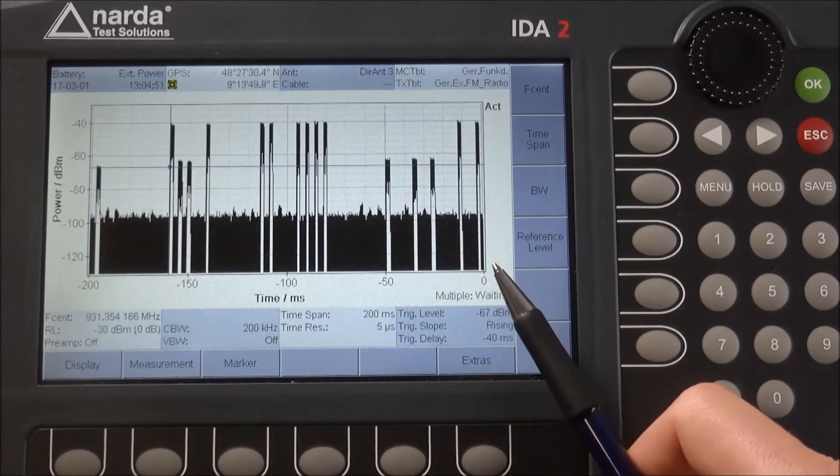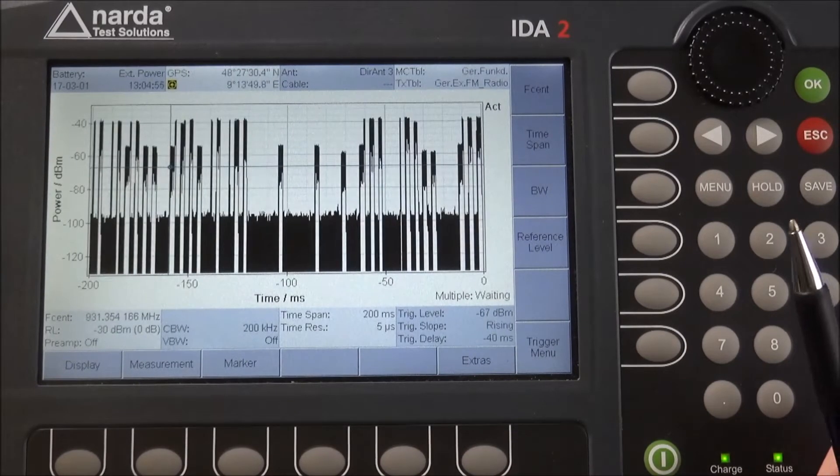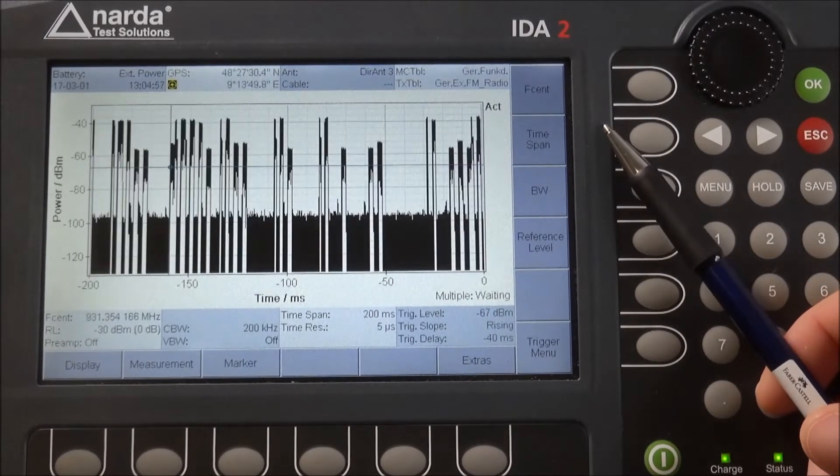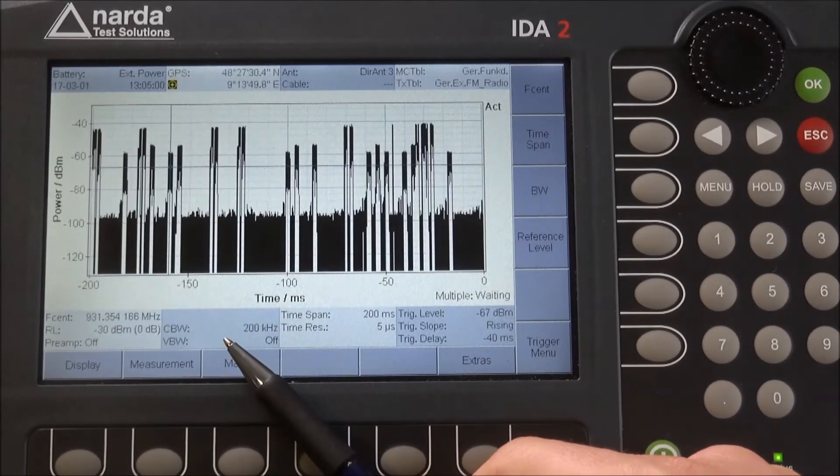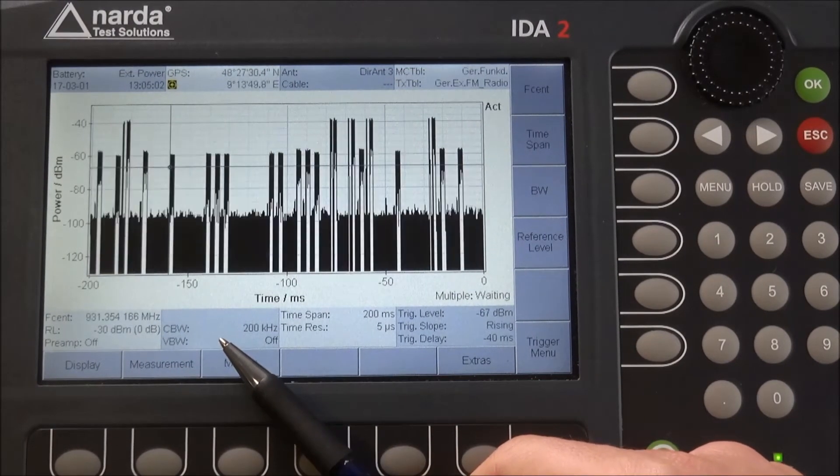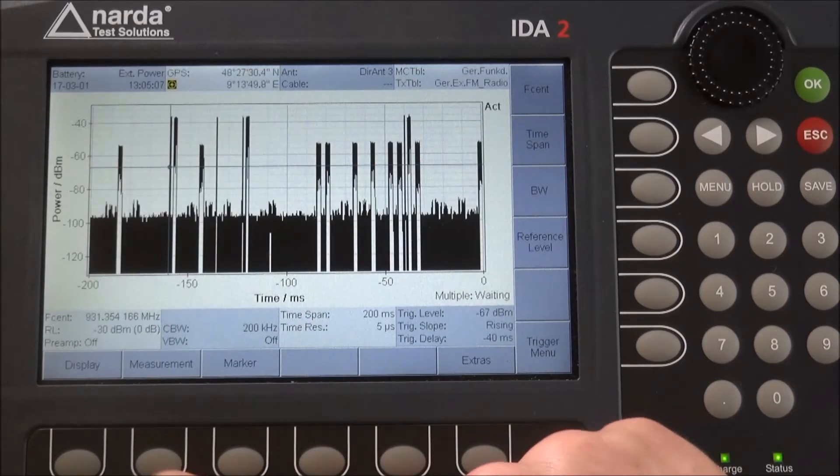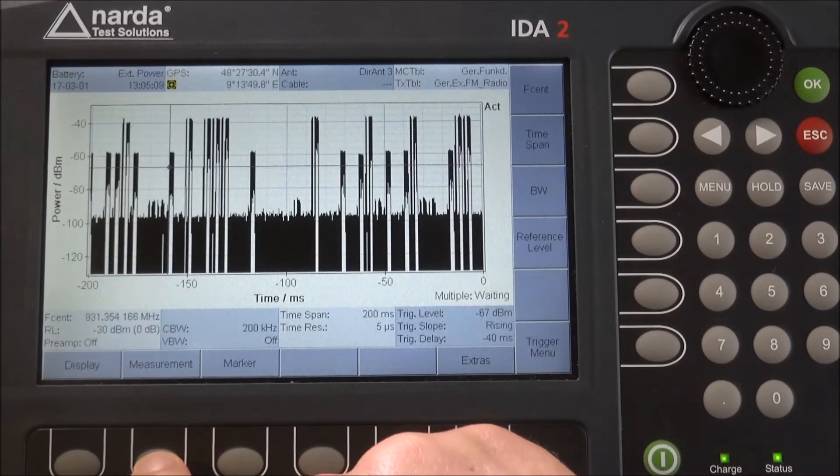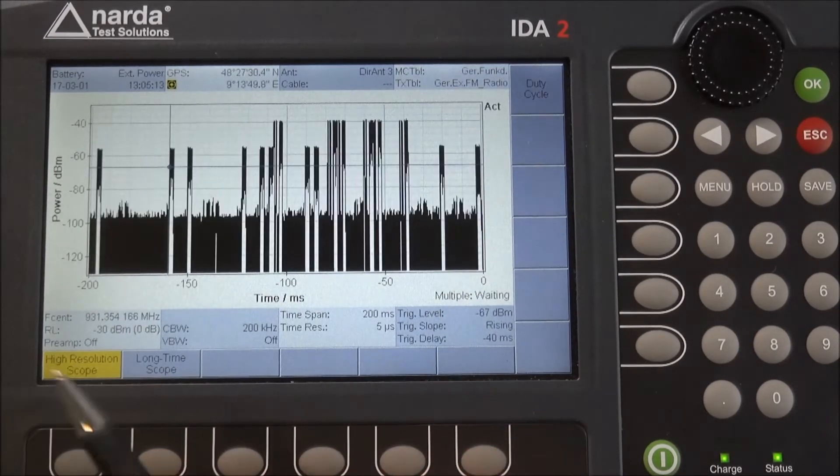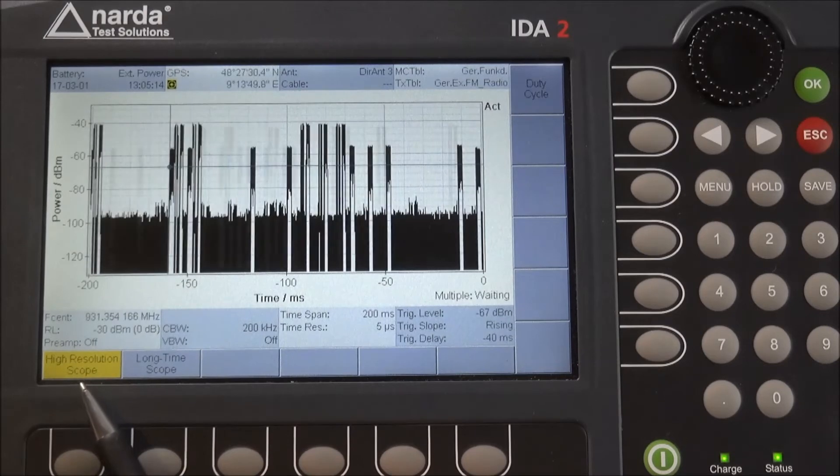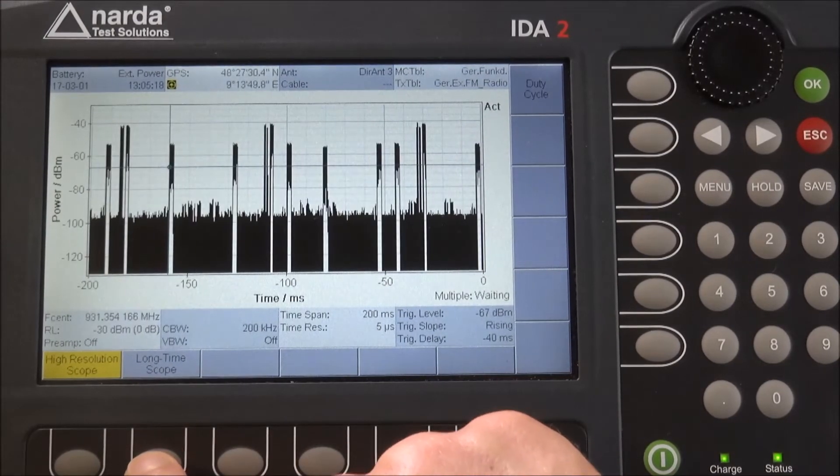There are some limitations with regards to time span that are influenced by the channel bandwidth and by the internal memory of the IDA. For that purpose, there is a sub mode when you click on the measurement at the bottom. This is the high resolution scope, but there is also the long time scope that allows you to record and watch signals for up to 24 hours.